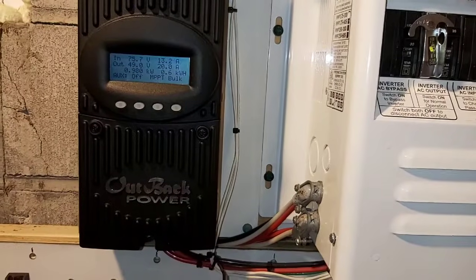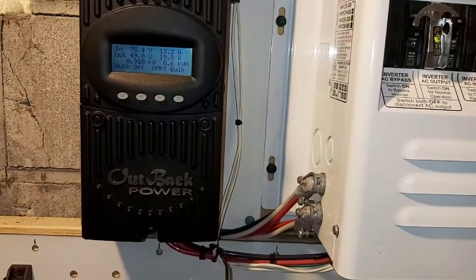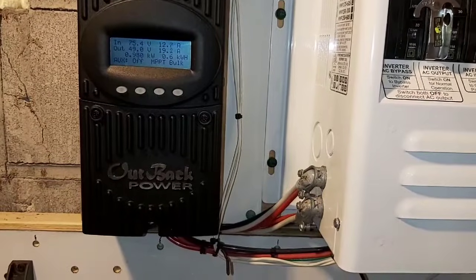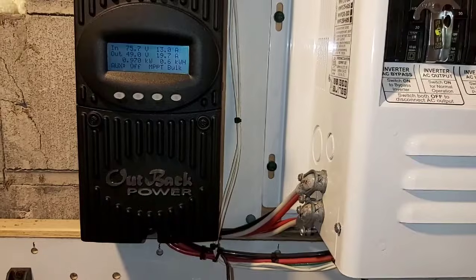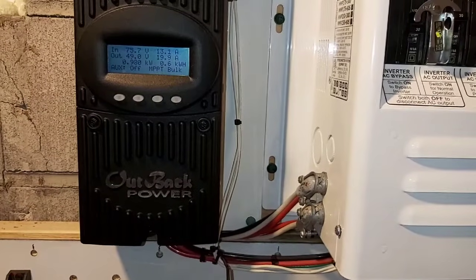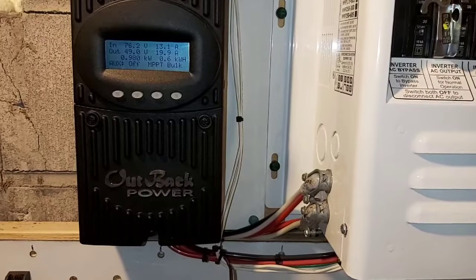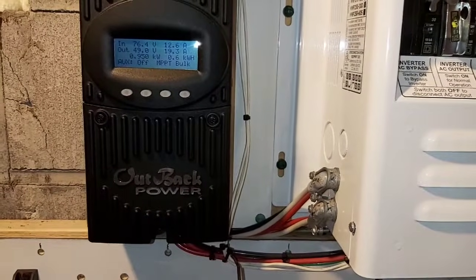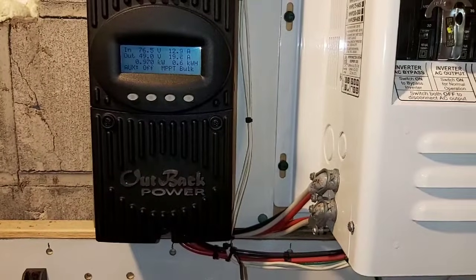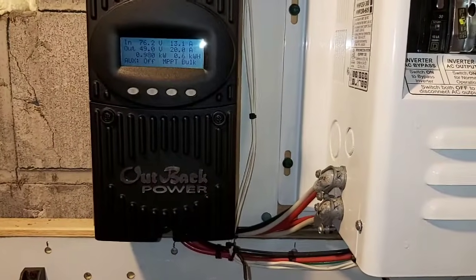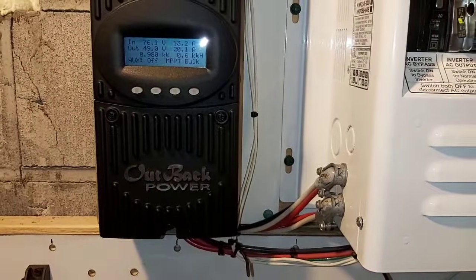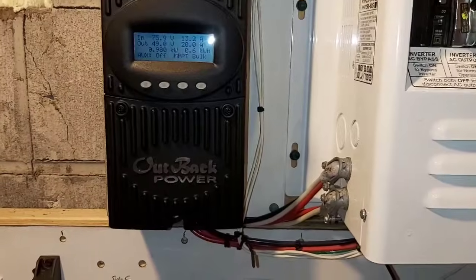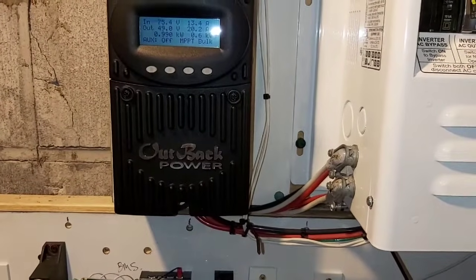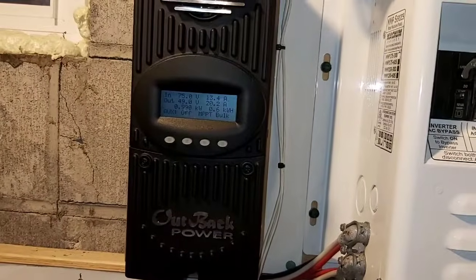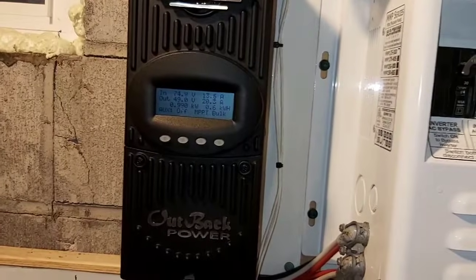We'll switch into absorption here shortly if we stay going 20 amps. We're at 49, so it's got to hold 49 for, I don't know, a minute or something before it kicks in. Then it shouldn't absorb charge for more than, I'd say at least no less or no more than 10 minutes, and it should flip into fully charged. But obviously if it keeps flipping back to 48.9 and up to 49, it's not going to flip over.